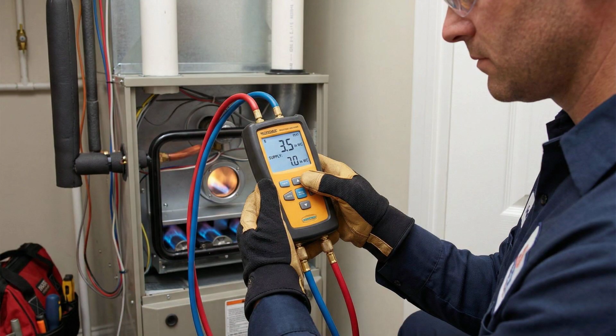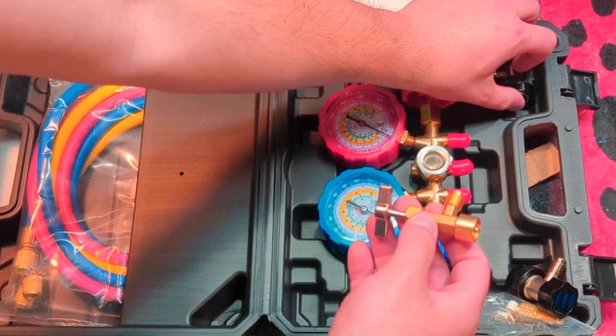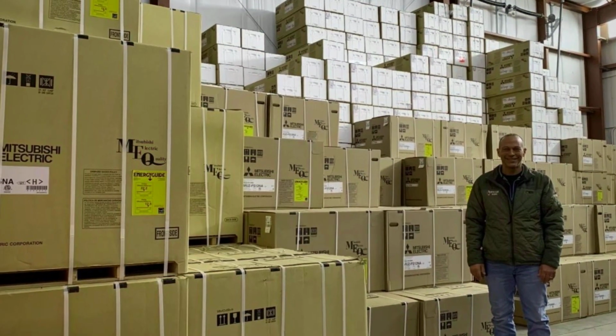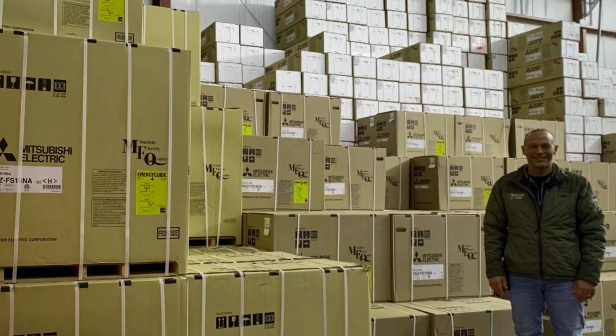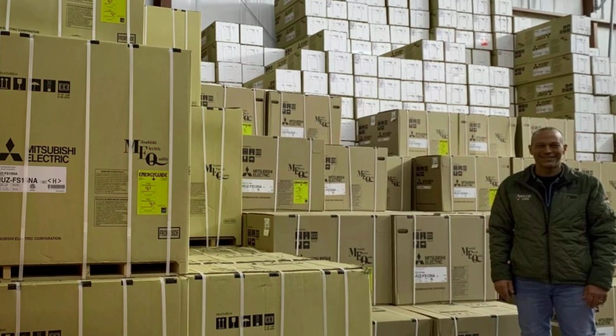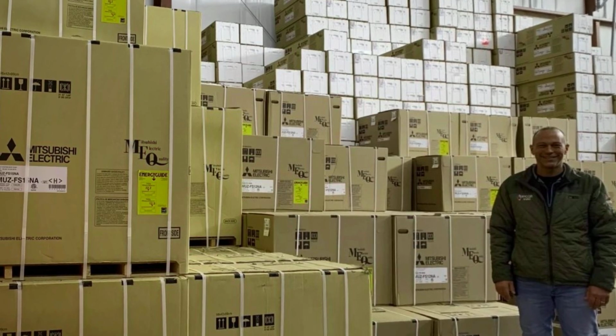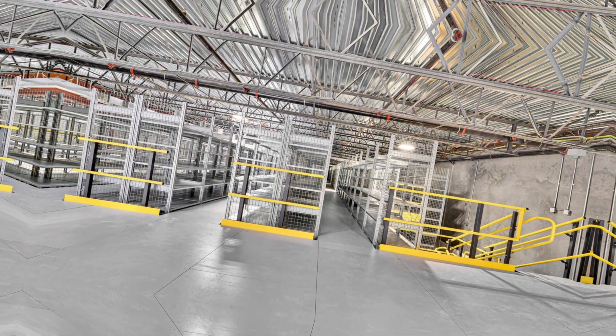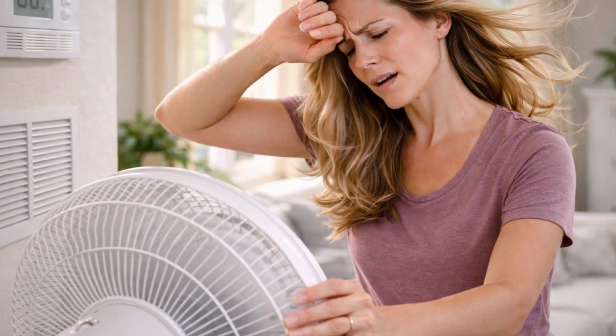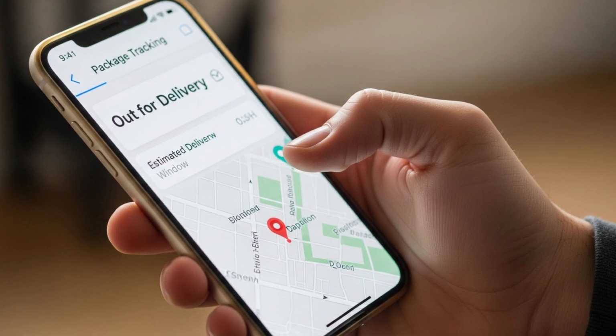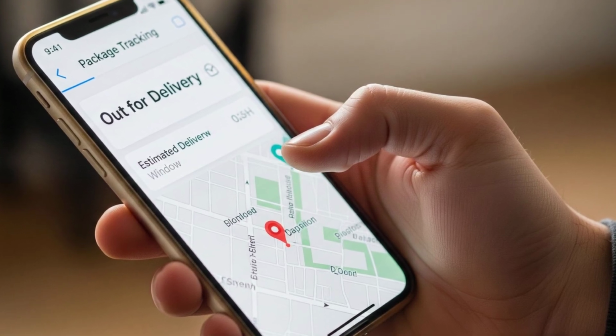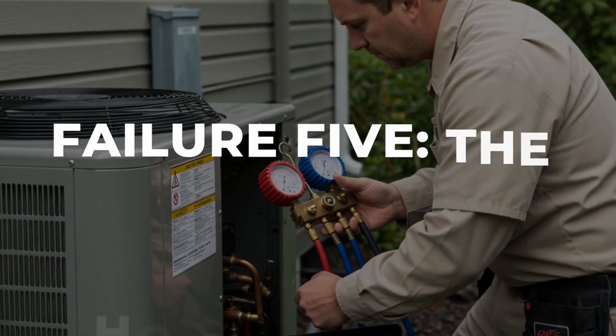And if the leak is anywhere else on the slab, a header connection, a manifold point, a different tube section, you are not repairing. You are replacing. The part is proprietary. The lead time is whatever the distributor says it is. Your house stays hot in August or cold in January while you wait for logistics to catch up with your emergency. Failure 5, the hostage map.